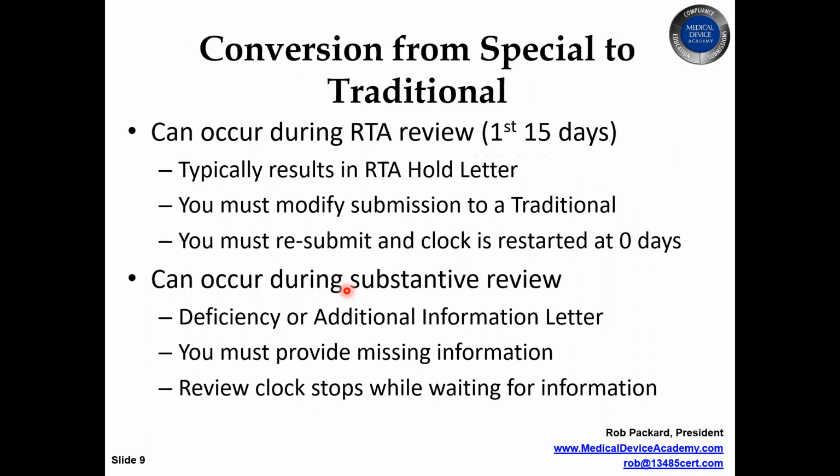So what happens when you get converted from a special to a traditional? What's happened is you submitted it as a special 510K, hoping to get an answer in 30 days. And the FDA says, sorry, no dice. You're going to have to do a traditional submission. Most of the time, they determine that in the first 4 questions of their RTA checklist, and they spit it back to you saying, sorry, this is not a special 510K.